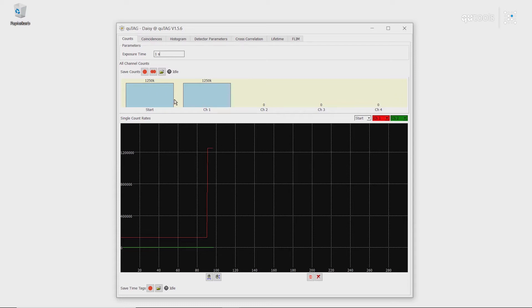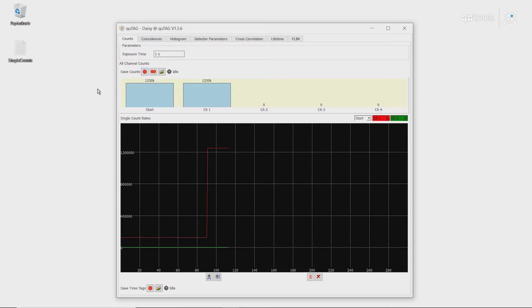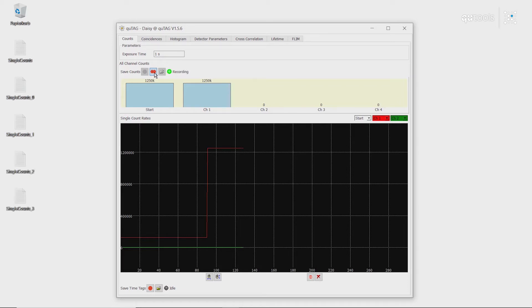We can also save these counts, so the number of counts per channel per exposure time, to a CSV file for later data analysis. If we want to change it to save a single file, we press this red button. We generate a CSV containing the number of counts per exposure time for all channels. We can also do this all in a row. If we click this button, and every exposure time, a file will be saved containing the exact same information.